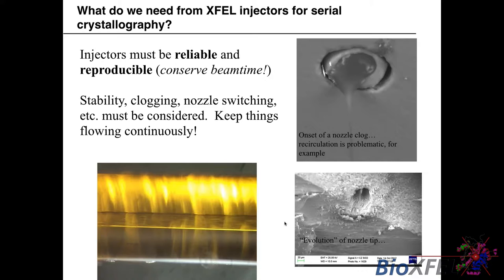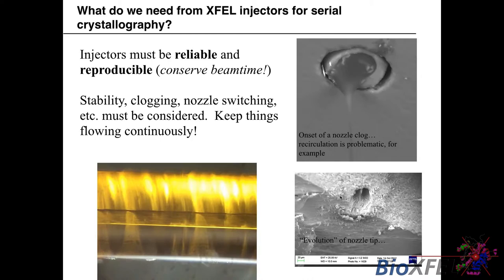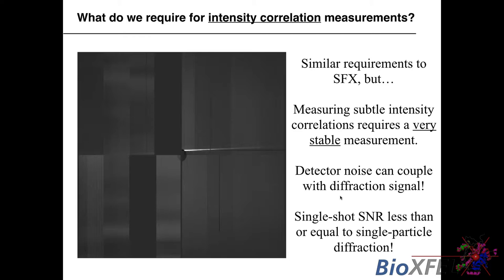We also need to deal with reliability and reproducibility of nozzles — avoiding clogging and making sure they run stably throughout an experiment. On the upper right you can see a clog forming on the tip of a nozzle: there's the liquid jet coming out and material accumulated on the tip, which can be difficult to track down during an experiment. On the bottom is aggregation of material from the buffer, showing that nozzles can evolve in time as the experiment goes on.